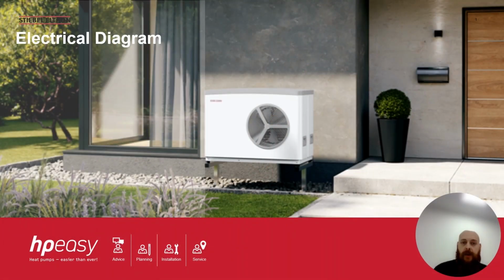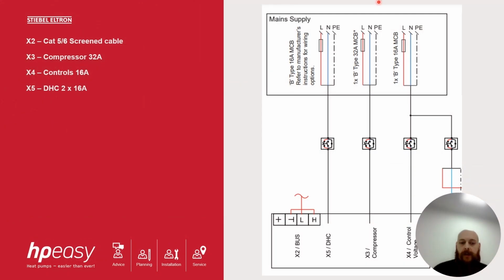In this section, we will look at the electrical diagram for the WPL 25 ACS. You will need the following supplies. So, firstly, we'll start with X3, which is our compressor supply. This is a 32-amp supply. And you will need a rotary isolator.